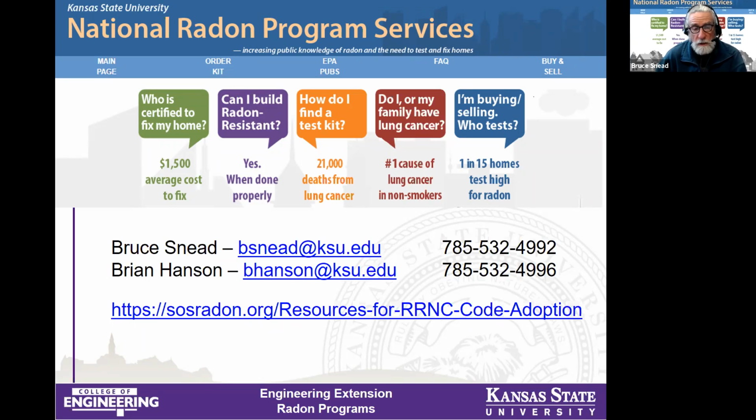It's far better to invest in making the building radon resistant from the get-go based on data and information about the location, the county, and the radon potentials there, looking at state data that may be available on the state radon program website. Obviously in some areas of the country, Louisiana, for example, maybe 2% of the homes might have elevated levels of radon. The potential is much less there than it might be in places like Iowa. So that's part and parcel of what can plug into it, but it doesn't make any sense to test the soil to find something that's already there that tells you nothing about what the ultimate level will be in a home or structure built on that soil.